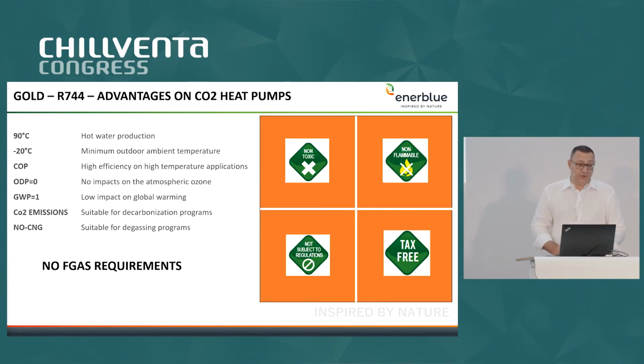Advantages of CO2 for the heat pumps. We can easily reach in our unit 90-degree leaving water temperature, even if we are working with an outdoor ambient temperature of -20. In the whole unit envelope, we can grant the highest COP possible, and in the same way, we have zero ODP refrigerant and 1 GWP refrigerant. So in this case, we are speaking about units that are excluded from F-gas regulation, so there are no several restrictions. We can reduce the CO2 emissions, direct and indirect emissions, and of course, we can propose this unit as a substitution for a system with compressed natural gas.